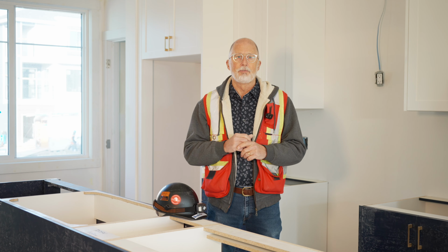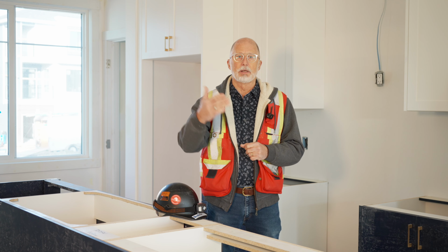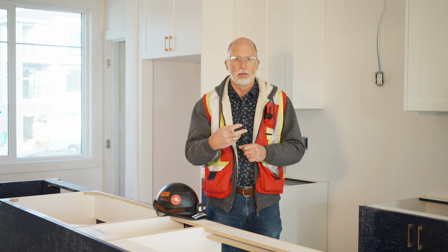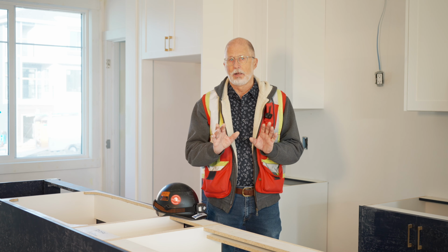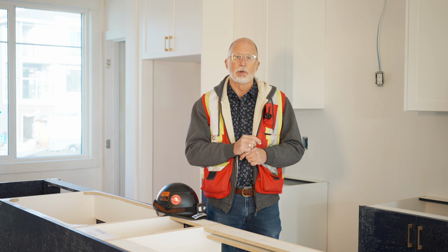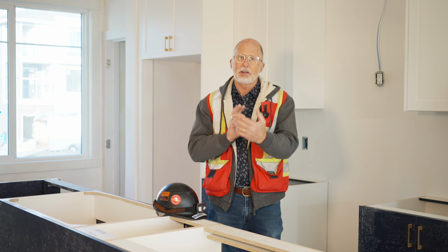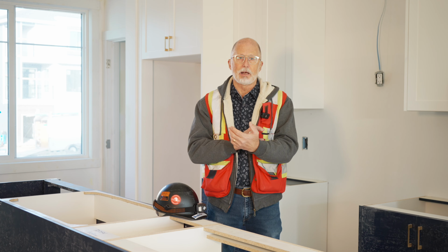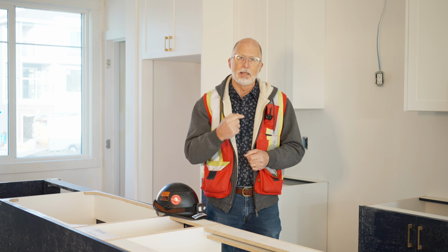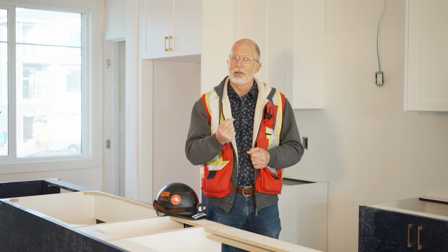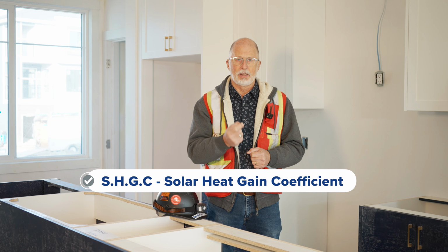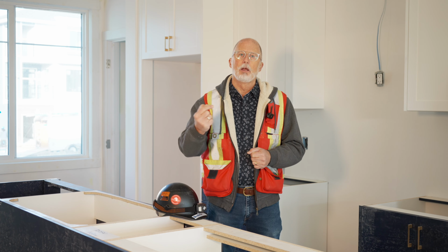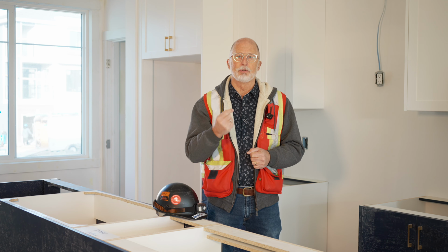So for instance, if you put lots of glass on the south side of a building, you get lots of free heat. Now, free heat in the summertime is not good. We don't want that. But we do want the free heat in the wintertime. So changing that direction will completely influence how that house performs with regard to the heat from the sun. And the reason for that is we have what's called in windows a solar heat gain coefficient, which is SHGC, and the amount of heat that comes from the sun through the glass into the house is influenced by that.